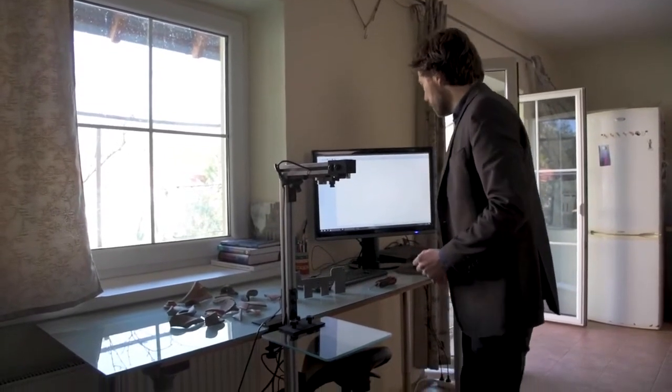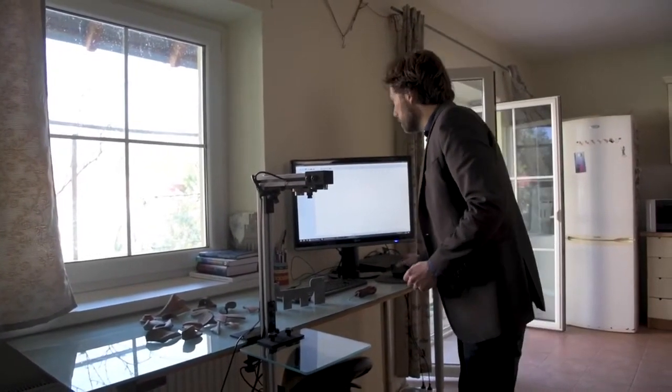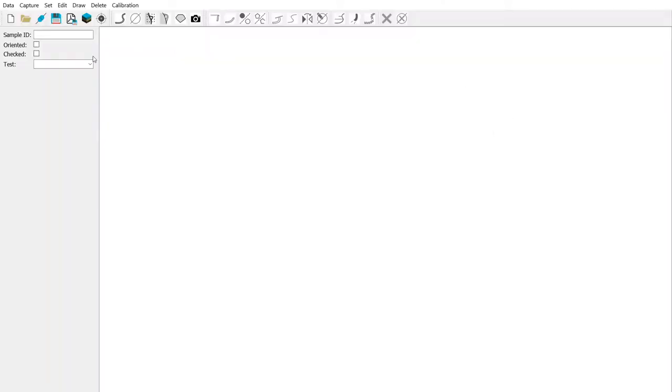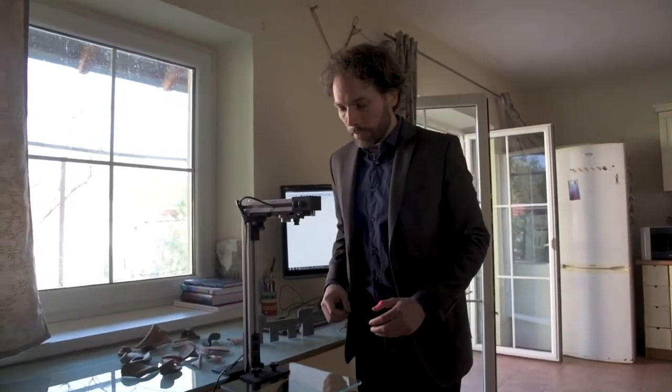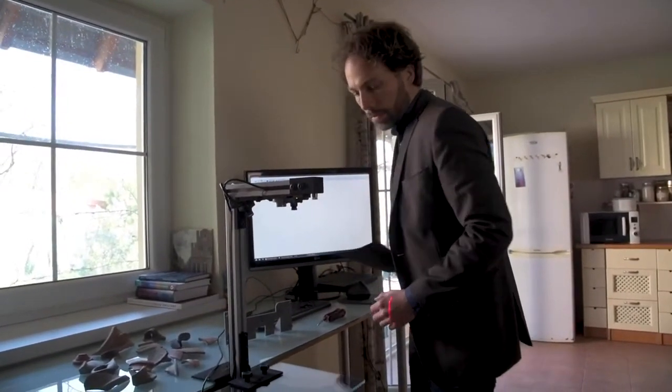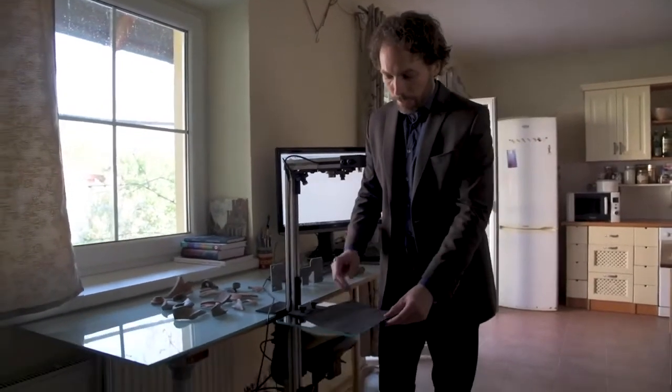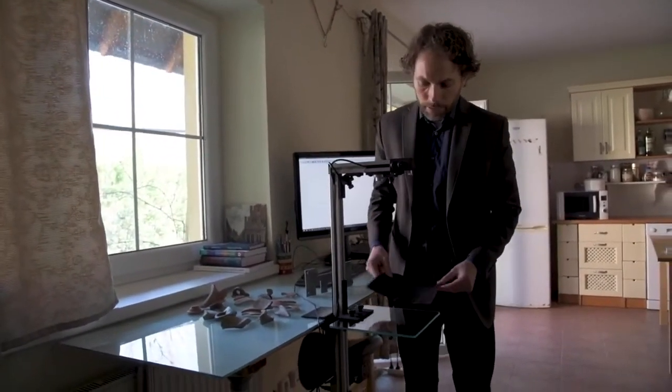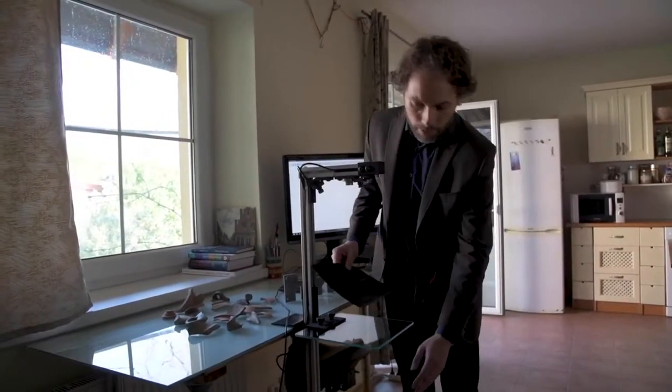So this is now the software of the laser edit profiler, opened. I click on the calibration icon. And here you see a set of icons to turn on and off the cameras, the laser lines, and the lights. So I turn on both laser lines, and now you see the laser lines. I can use this paper to visualize them. They are a bit misaligned. That can happen during transport and so on.